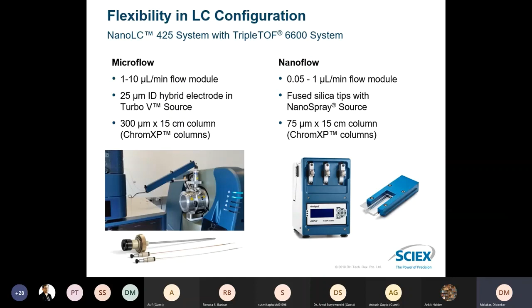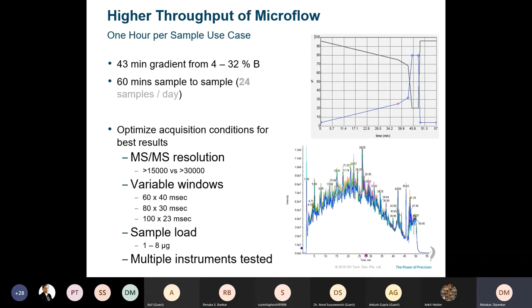This is one example where we can see a 1 hour run time per sample with a 43-minute gradient, and a good number of identifications obtained in this case. It shows MSMS resolution of 15,000 to 30,000, and variable window SWATH was used for analyzing the data. Sample load is from 1 to 8 microgram based on the complexity of the sample, and multiple instruments were tested.